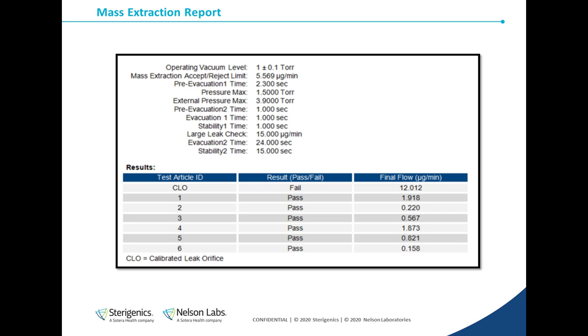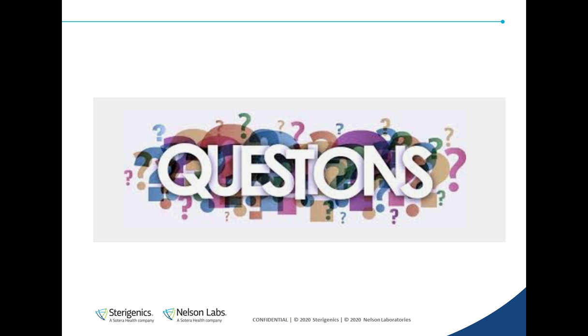The final report will contain some critical method parameters, including the Pass/Fail Threshold value and the pressure limits and some timing steps. Final flow values and the corresponding pass or fail determination is given for each sample in the results table. The CLO value is also reported so you can compare it to your sample results.